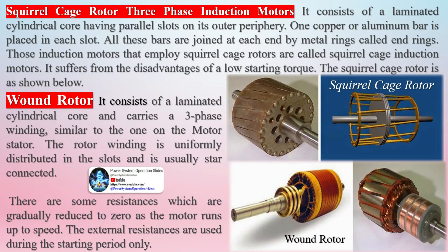There are two main types of rotors available in the induction motor: the squirrel cage rotor and the wound rotor. The squirrel cage rotor consists of a laminated cylindrical core having parallel slots on its outer periphery. One copper or aluminum bar is placed in each slot, and all these bars are joined at each end by metal rings called end rings. Induction motors that employ squirrel cage rotors are called squirrel cage induction motors. This type suffers from the disadvantage of low starting torque.